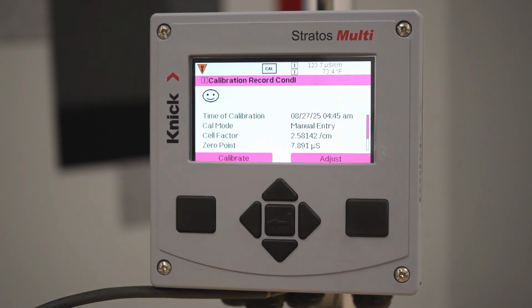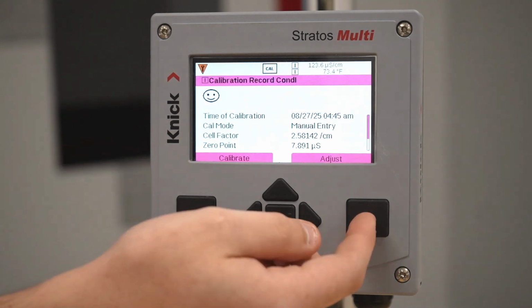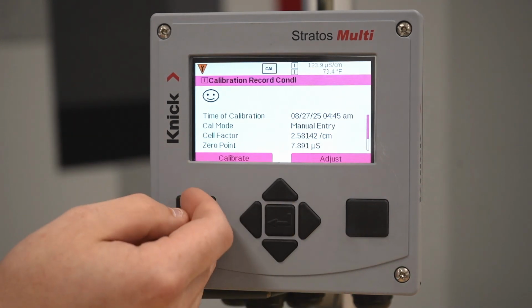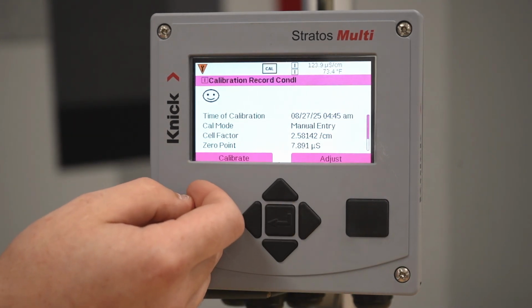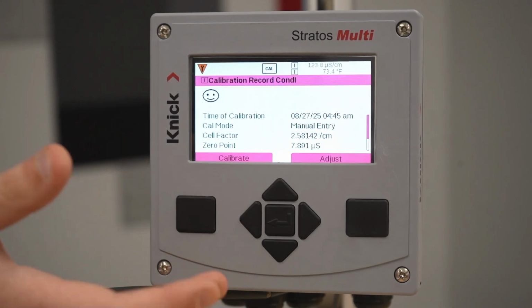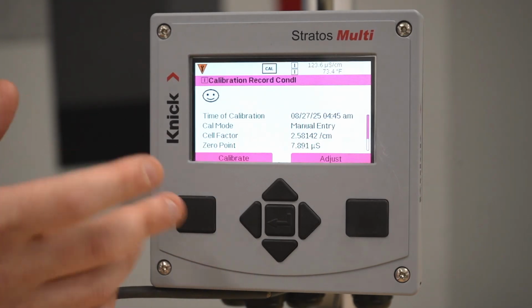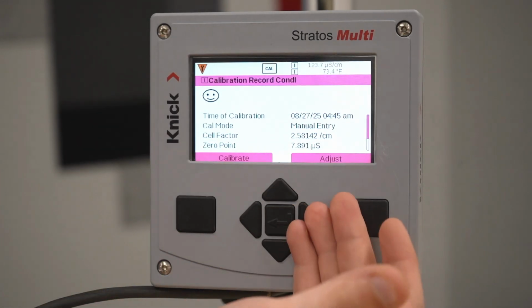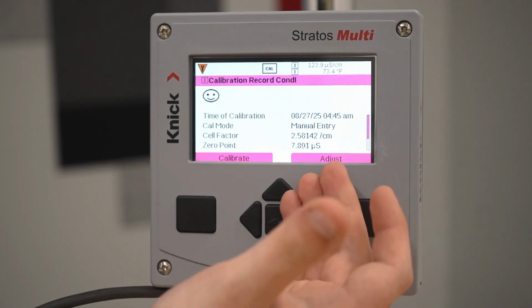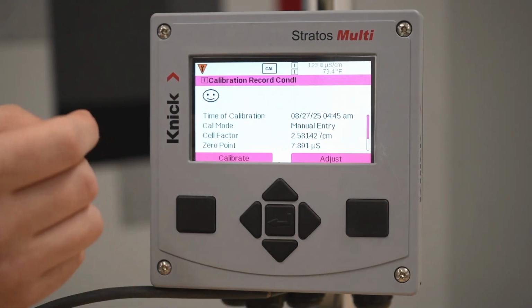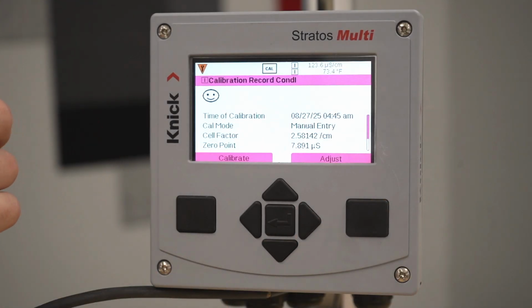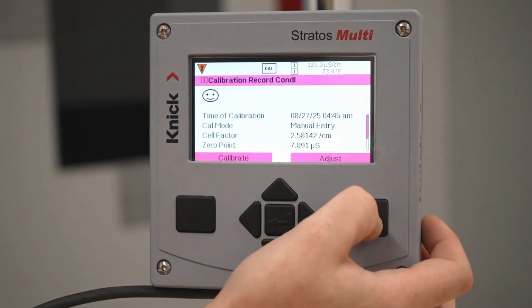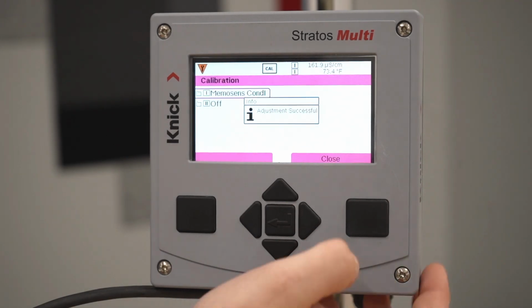And then here you're going to be presented with two options. And just to clarify it, you're going to have calibrate and adjust. The difference here is a calibration is a temporary calibration and it won't save to the probe, meaning if you take the probe elsewhere after disconnecting, it won't be saved. However, if you choose adjust, this will actually save the calibration into the head of the probe itself, and it will be good to go wherever you take it. So we're going to adjust, and then we're all done.